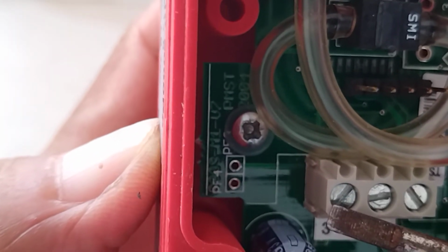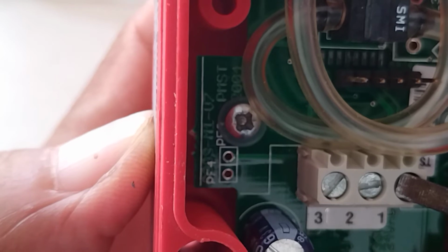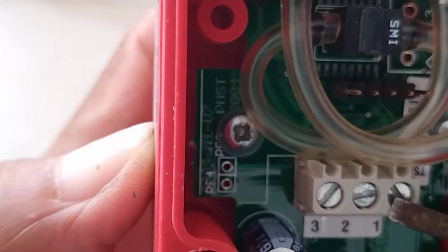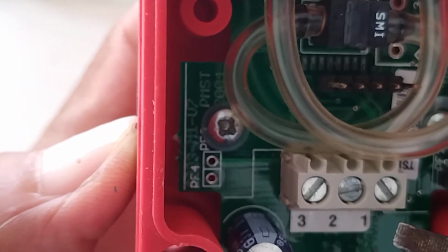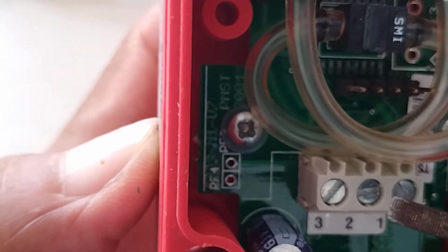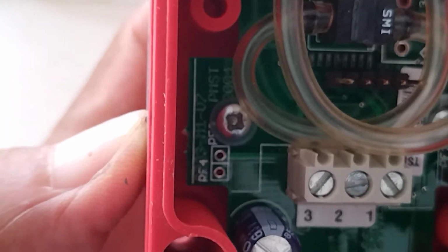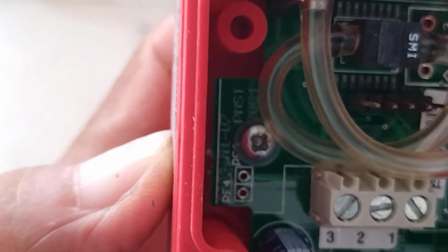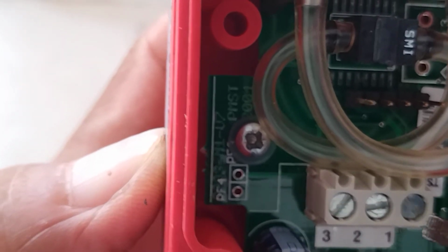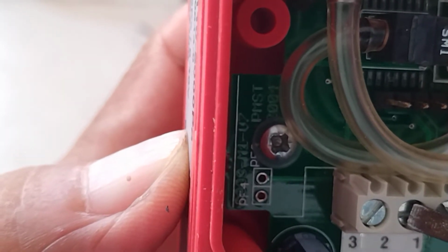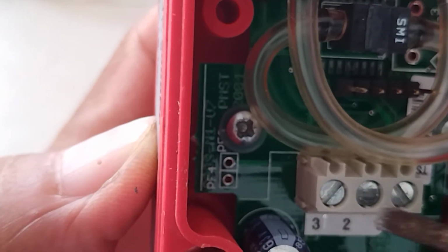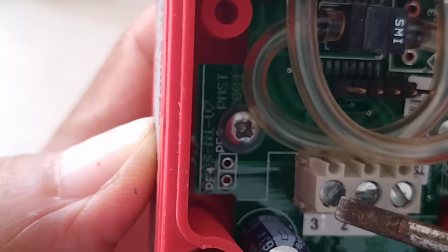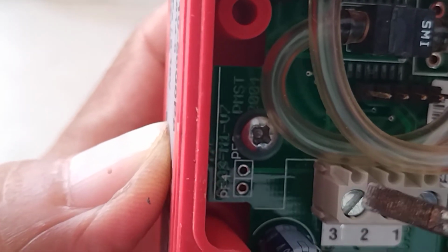So 0 volts, then 24 volts, then the control signal that this device will give us will be here. You also need two wires there, a two core cable. The signal will come from this terminal, and then you can share the common here.